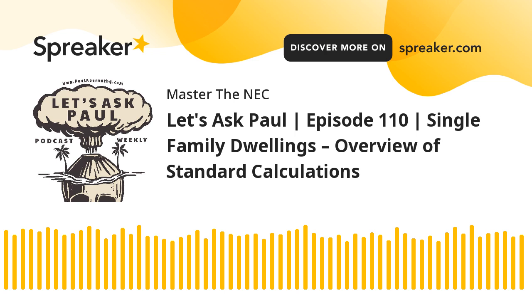So on an exam, for example, if they don't tell you the number and they want you to do a load calculation on a one-family dwelling, then you have to assume at least 2. In the real world, if you have more than 2, you have to account for those. If you have multiple small appliance branch circuits, then you have to take them into consideration.